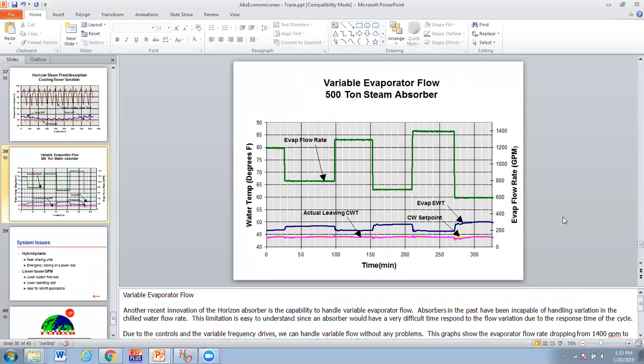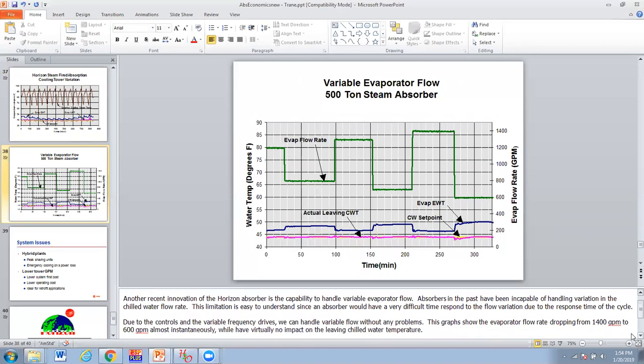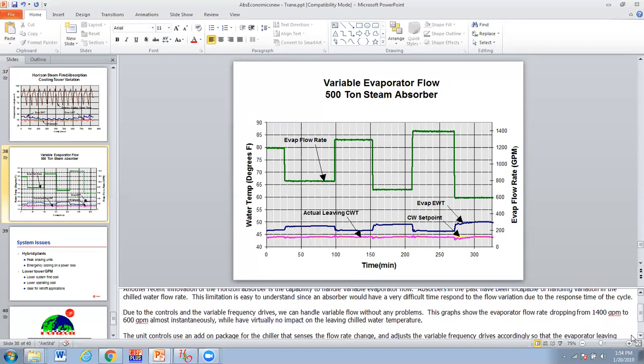This one shows, so these days in chill water system design, in order to save pumping energy, they've developed a concept called variable evaporator flow. In the old days, the rule of thumb was you didn't or couldn't or shouldn't vary the flow through the evaporator. That's where the refrigeration effect was actually going to happen. These days, it's pretty standard stuff, and you can reduce some pumping energy by doing it. And so they're showing the ability here to do this on an absorber with variable evaporator flow. So in the past they couldn't do it, etc.